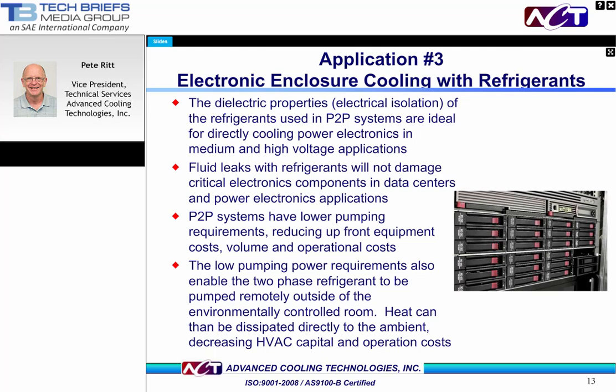Our final example of P2P applications is for cooling high-performance electronic enclosures. In many of these applications, such as data center cooling and energy delivery and other power electronics, there is a requirement for high reliability. In these applications, a potential catastrophic leak from a water cooling system must be avoided. As such, there is a requirement for a dielectric working fluid, which means refrigerants are necessary.